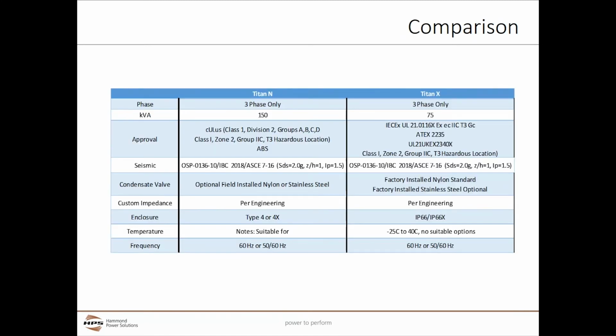In terms of comparison to our Titan N line, there are a few differences. Our Titan N encapsulated transformer goes up to 150 kVA, while our Titan X is up to 75 kVA. Our Titan N has cUL US approval for Class 1 Div 2 or Zone 2, while Titan X has IECEx, ATEX, as well as UKCA Class 1 Zone 2 approval. Both of these lines are seismically approved for OSHPD.